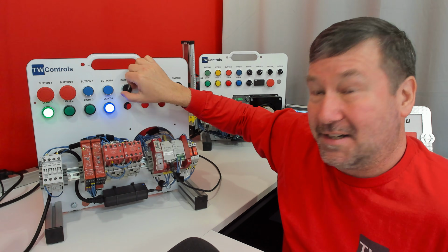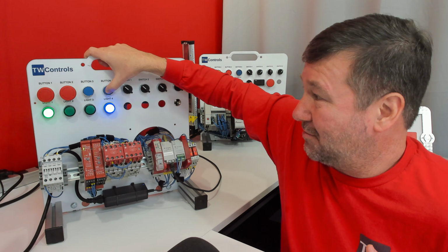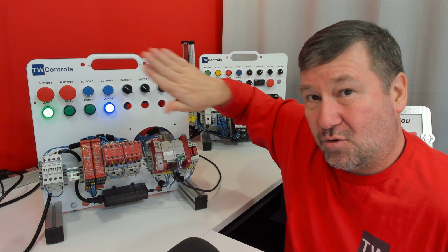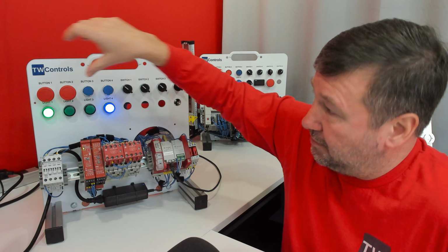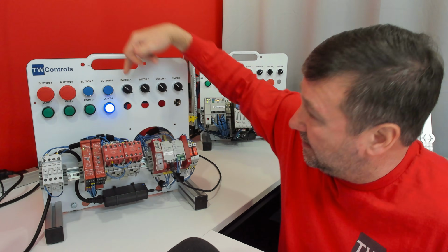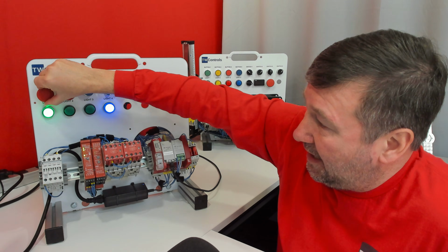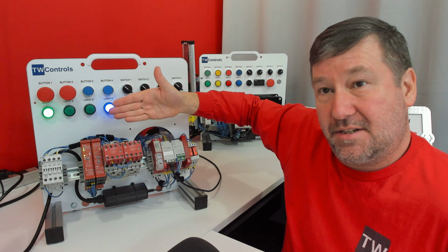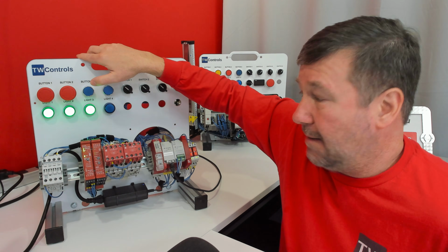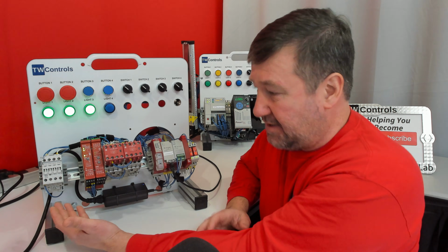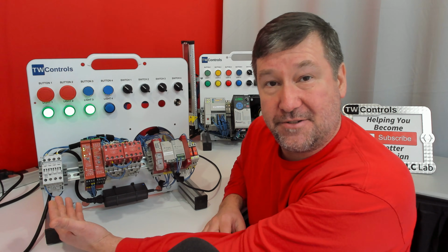Now, we fix our e-stop. It's still not going to let us reset. It's going to have to see a transition of both of those contacts going from false to true. So we press the e-stop again now that we're repaired, and we pull it back out. That's going to let it see that transition of trues and falses. And now to reset.